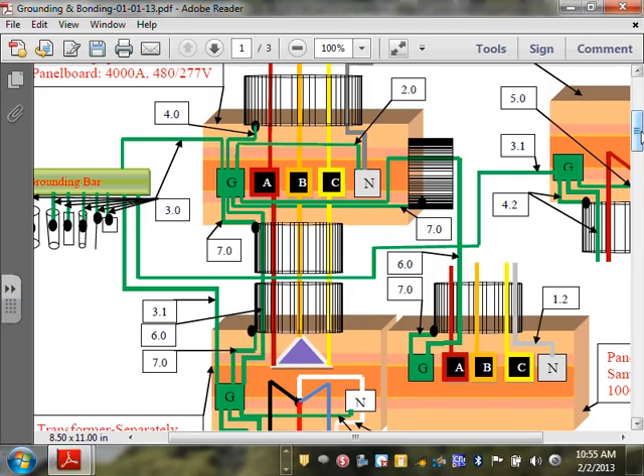Because what happens here, if you have a ground fault in this system, let's just say if you have a ground fault right here, part of the current is going to go right through the equipment grounding conductor, right, to the service. The other part is going to go through what? Through your EMT or rigid conduit. So you have to bond your EMT or rigid conduit on both sides with the proper bushings or clamps because both of them will be acting as an equipment ground conductor under a ground fault condition. Any comments, guys? Any questions?